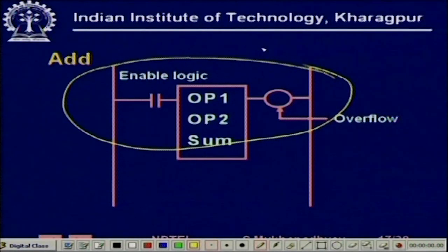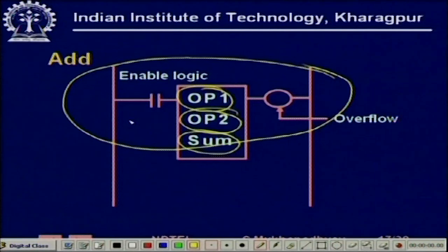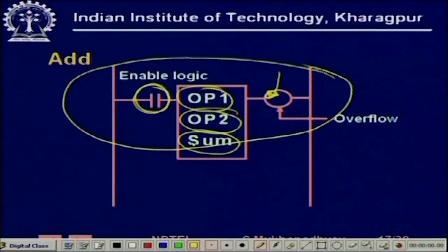In our format, this rung diagram represents an addition operation: when this rung is executed, operand 1 and operand 2 will be added and their sum placed at the location 'sum', provided the enable logic is on. The output coil may indicate an overflow condition during summation, which can then be used in further logic. Similarly you could have subtract, multiply, and various other arithmetic instructions.